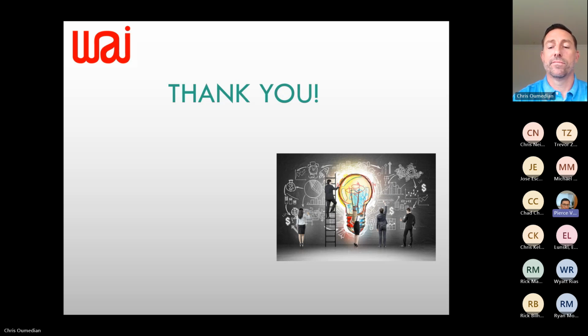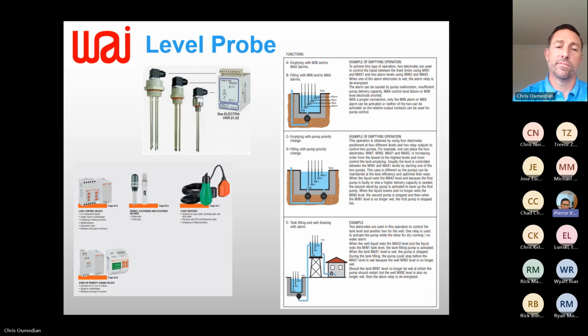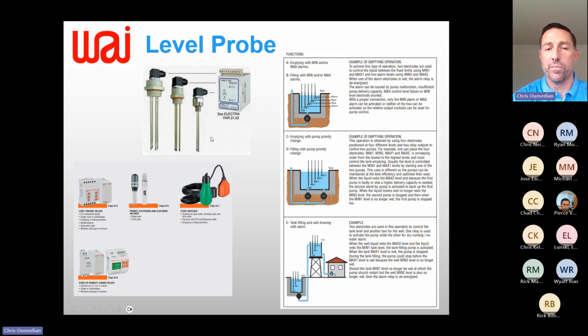Chris, those level probes, I missed the technology behind them. Is it a conductive thing? It is, those are conductive probes. As the media goes up, you'll see this one over here. The easiest one to envision is this one. You've got 2 probes. Think of putting your hand in a socket and your feet in a puddle of water, that's what's going on here. When the media touches those 2 probes, they conduct across each other, generating power, voltage and current. As the media comes up, it closes that loop and tells you the media has hit the bottom of those 2 probes. So it's a known resistance up the probe so the probe knows where the media is along the length of that probe.